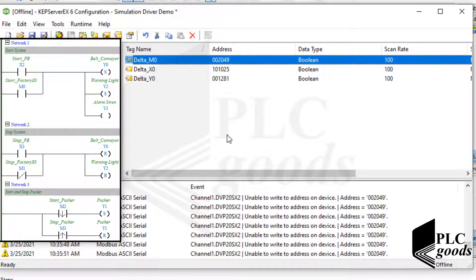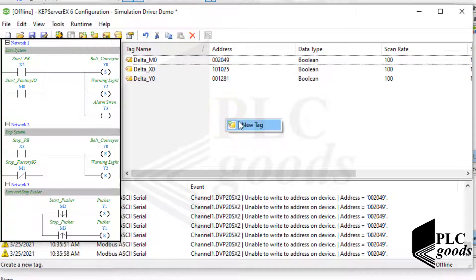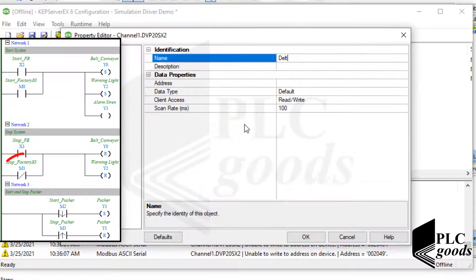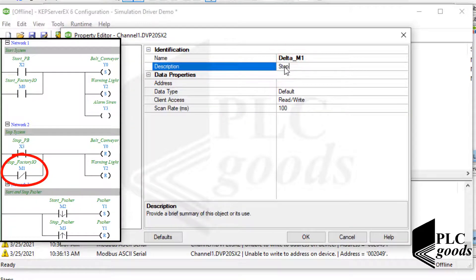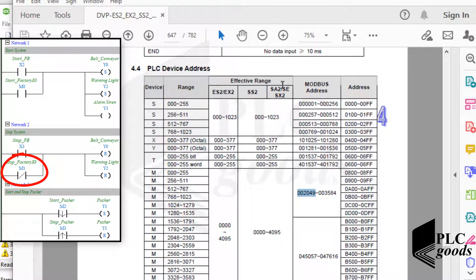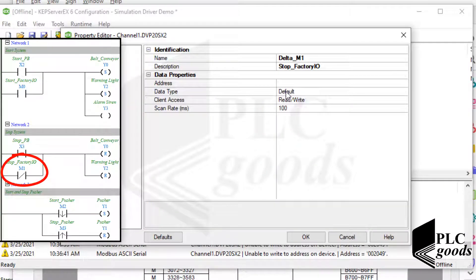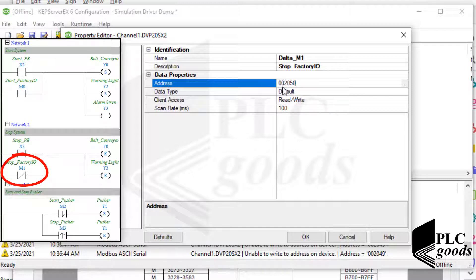Let's start with the memory addresses. I've defined this tag related to M0. Now let's create another tag related to M1. Note that I want to connect this memory bit to the stop push button. The Modbus address related to M0 is 002049, so the Modbus address for the next memory bit, M1, is 002050.